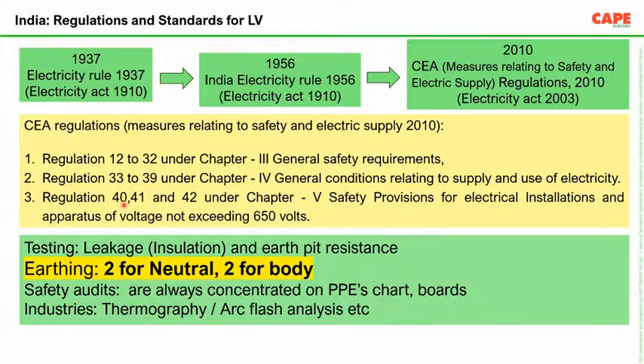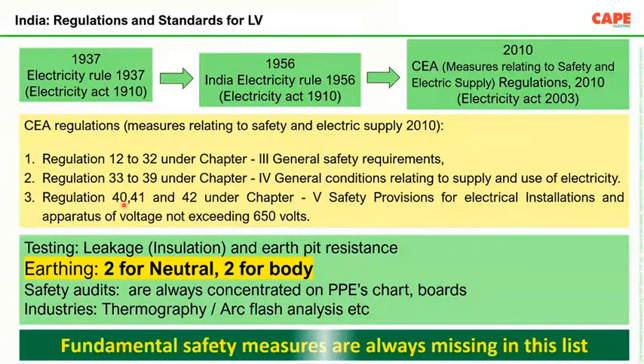And nowadays in industry, thermography and arc flash analysis are done. Actually, thermography and arc flash analysis are an extra safety measure. You do the basic safety measures properly. Once your basic safety is ensured, then you do these measures extra. That means the 10 different tests and the 16 inspection points. After doing the tests and the inspection, if the customer has money and wants further safety, you can go for thermography and the arc flash study. But the fundamental safety measures are always missing in this list.